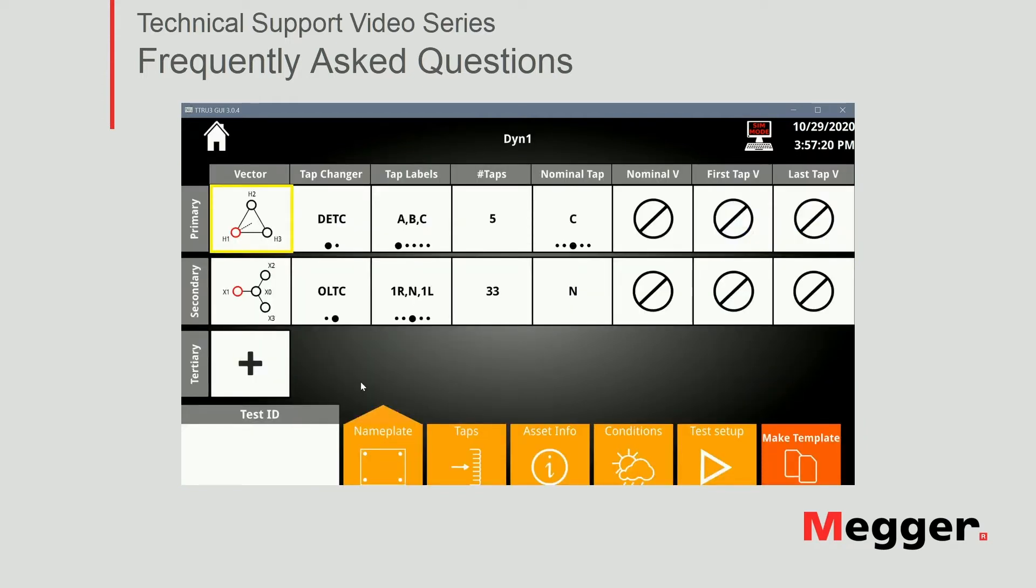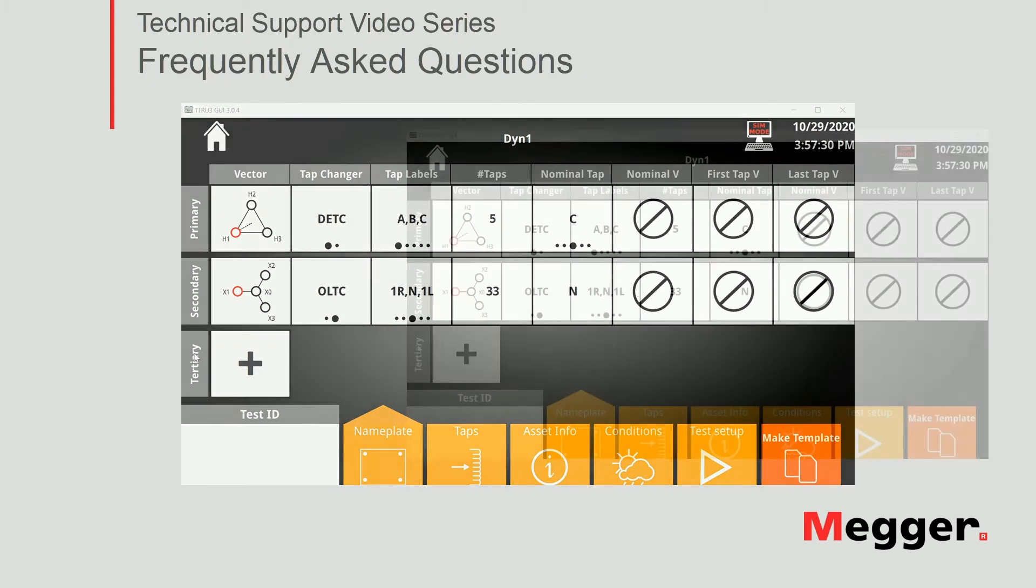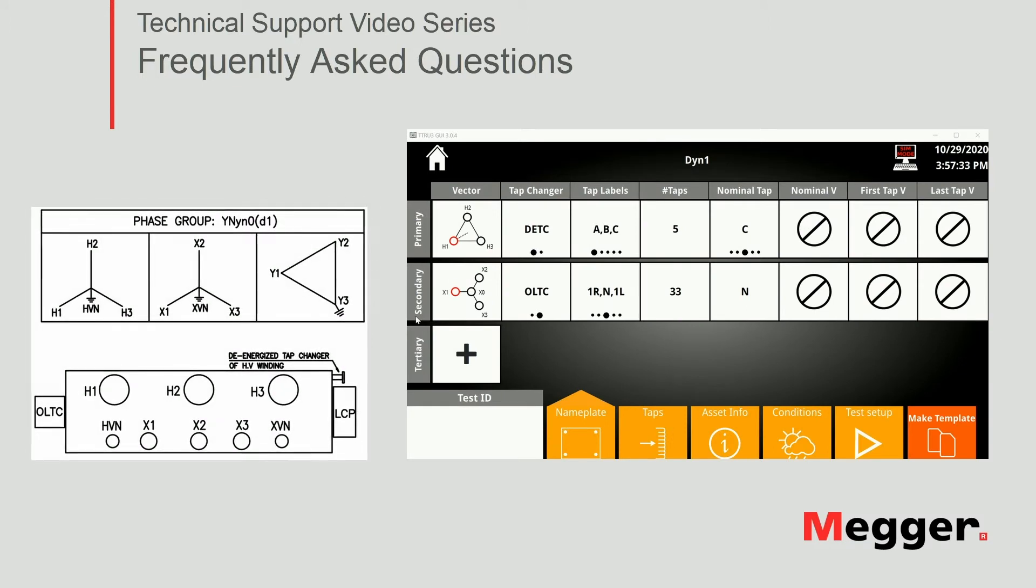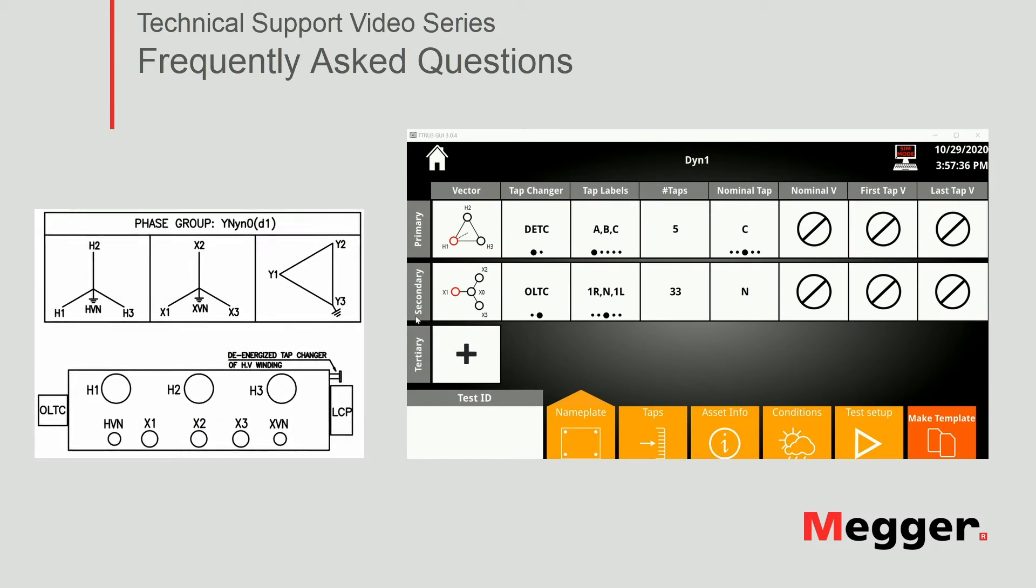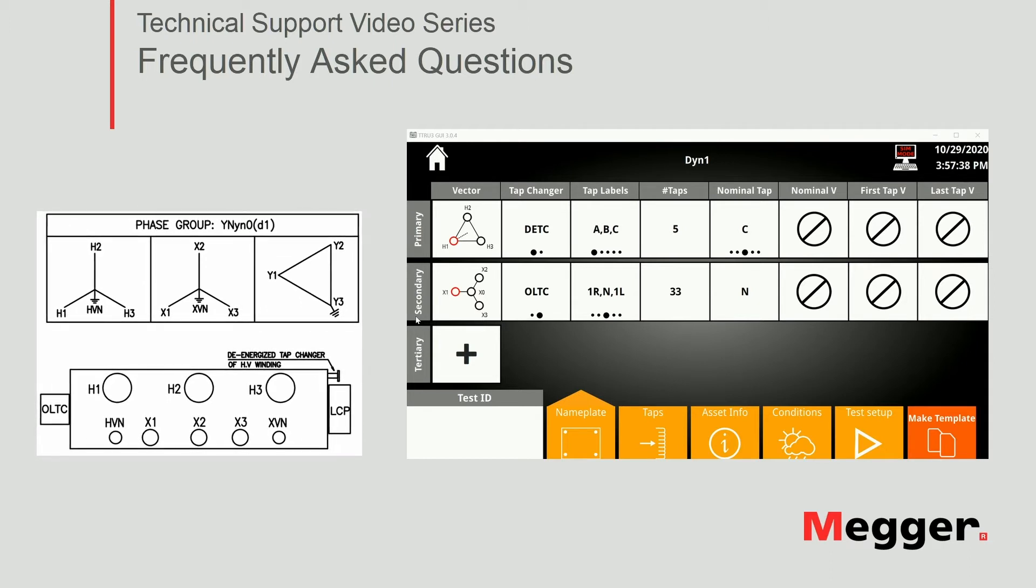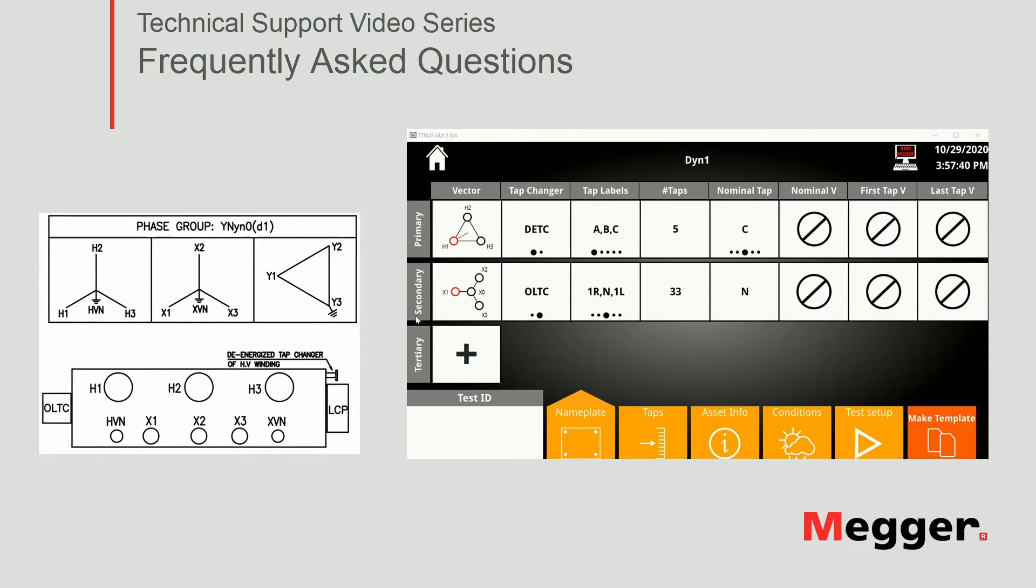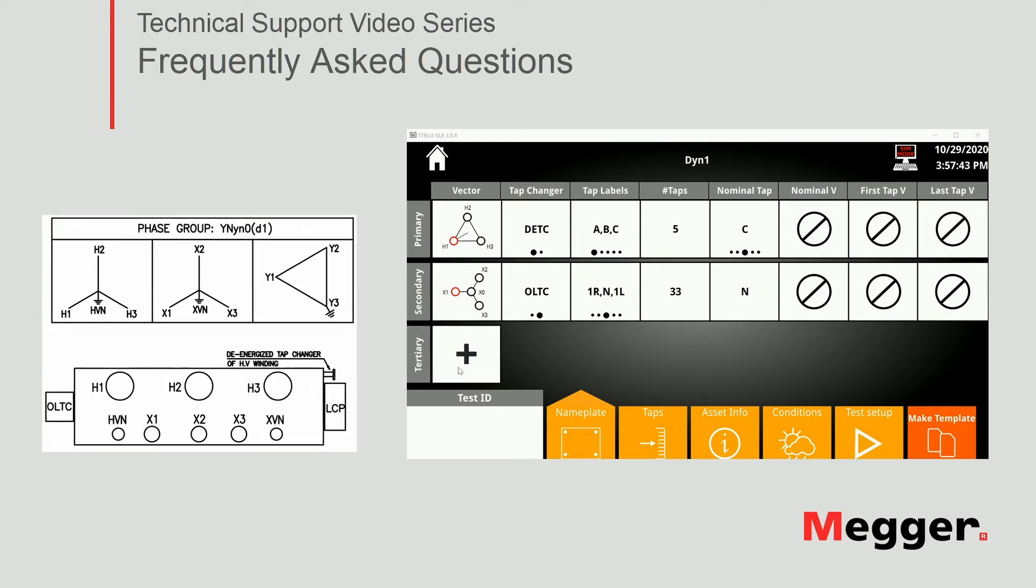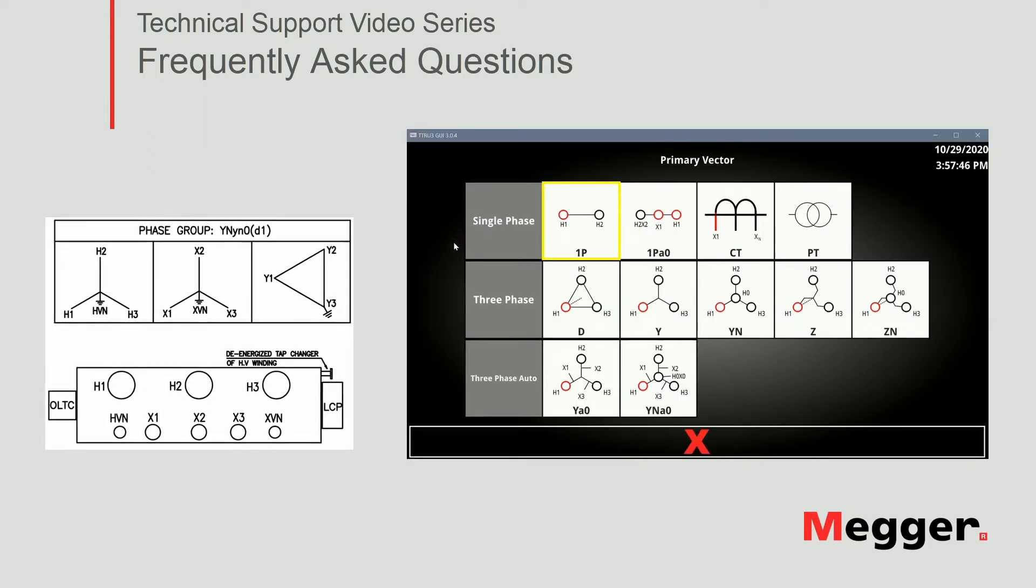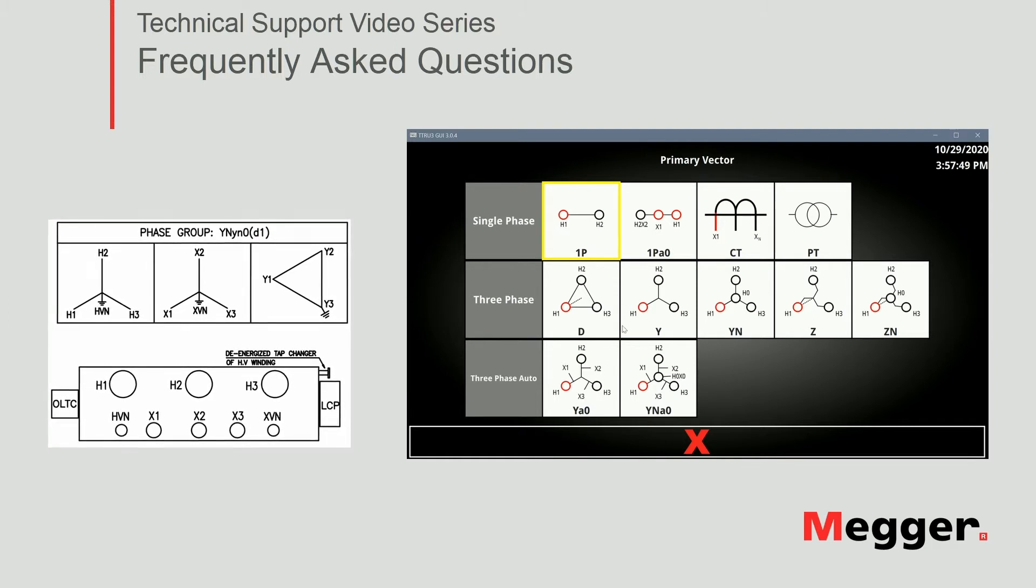The software will remember the last configuration you used. Of course we're going to fill out this section according to the transformer nameplate we are testing. In this case we can see here in the phase group indicated in the nameplate we have a YN, YN0 with a tertiary delta. We're not going to cover the delta test but we're going to put it in the nameplate as that is what the transformer has.